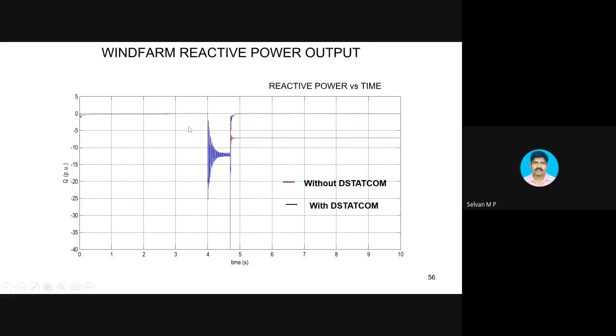And see the reactive power also, we have to have a reactive power at this point. See, with D-STATCOM, the reactive power requirement is brought back to the original value, which is nearly zero. Otherwise, there is a reactive power requirement of around minus 7 kVA. Means from the grid, it is going to take this much kVA. Then the grid will become completely burdened and the voltage collapse may occur, right?